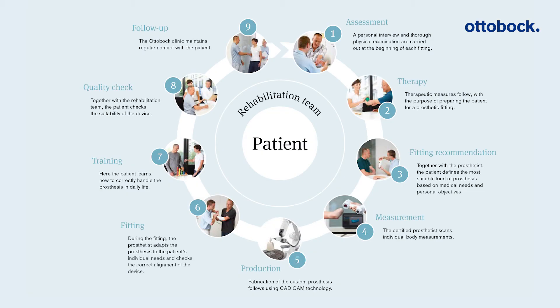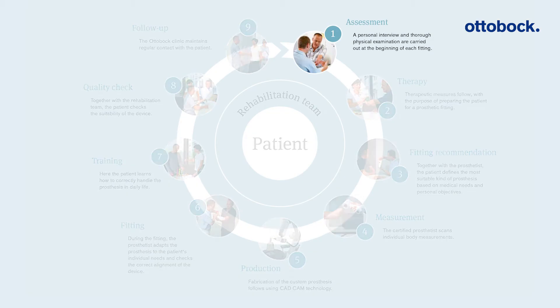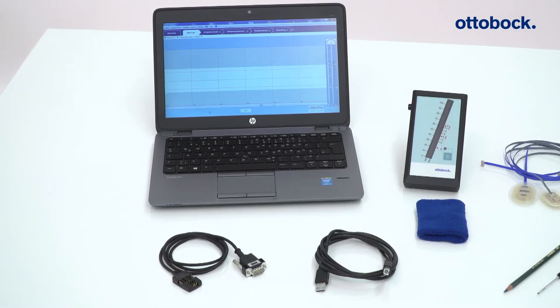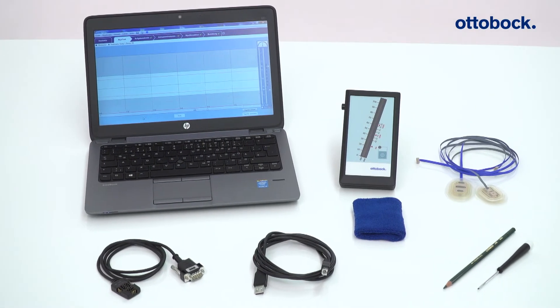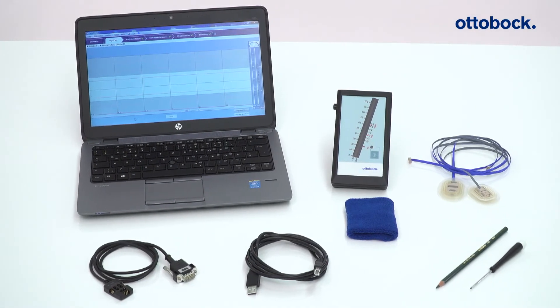Evaluation of the myosignals must be completed prior to definitive prosthesis manufacture and fitting. Preliminary evaluation will help determine the ideal electrode position and gain, as well as the most appropriate switching mode. The following components are necessary for a successful evaluation of the myosignals.